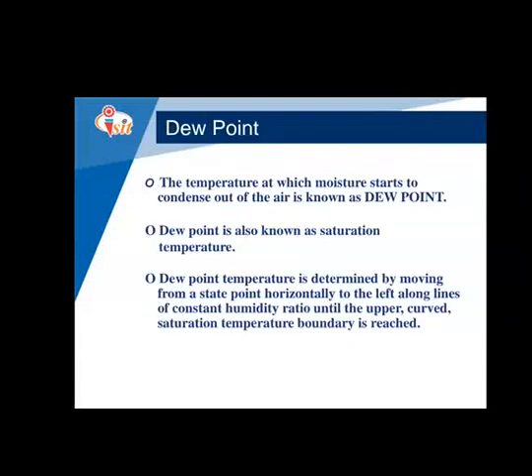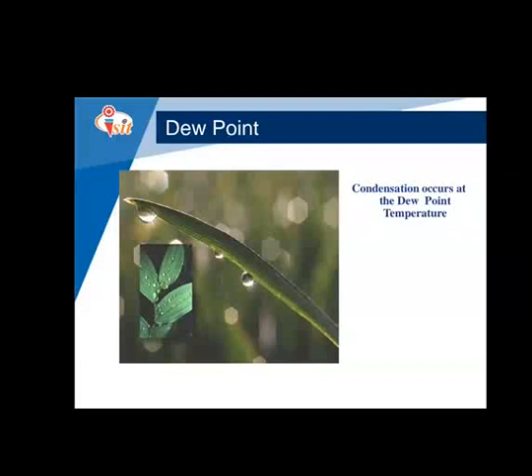First, we will go through dew point temperature. The temperature at which moisture starts to condense out of the air is known as the dew point temperature. For example, in the morning, dew is deposited on vehicle mirrors — that condensation occurs at the dew point temperature. Dew point is also known as saturation temperature. It is determined on a psychrometric chart by moving horizontally to the left from the state point along lines of constant humidity ratio until the saturation boundary is reached.